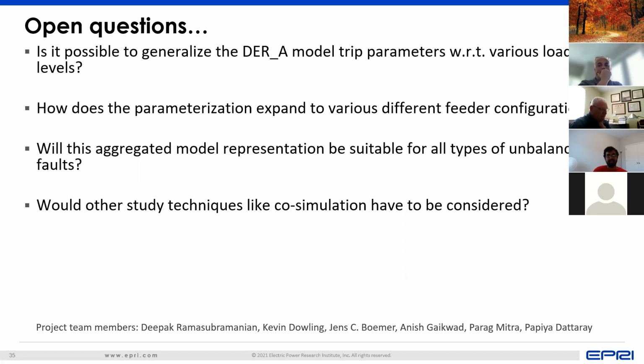Yeah, the other thing that can occur there is, as you said, it's both a blessing and a curse, because being spread out means that the possibility of one particular feeder or substation failing may not cause that much of an impact on the system. But at the same time, if it's so spread out, say a voltage event occurs at the 230 kV transmission level, or maybe even at the 500 kV transmission level, that voltage event may now be felt across a wide area.